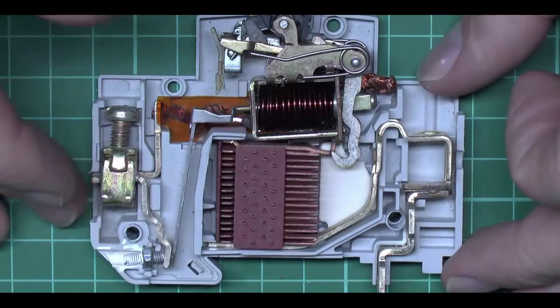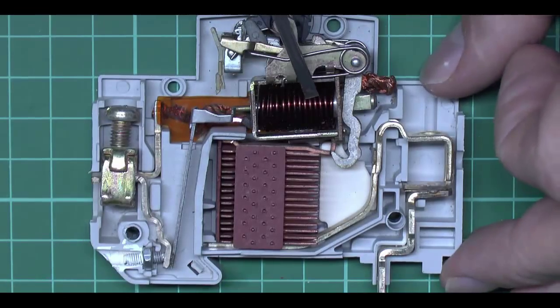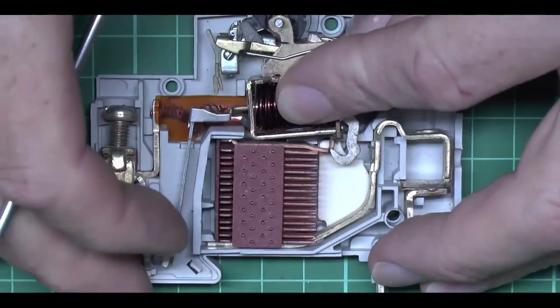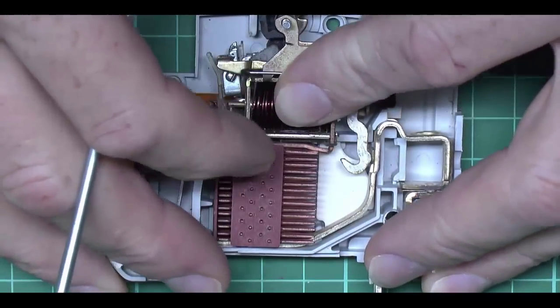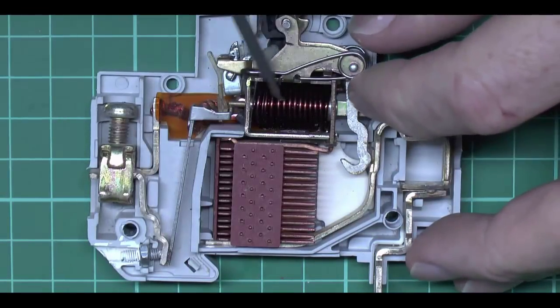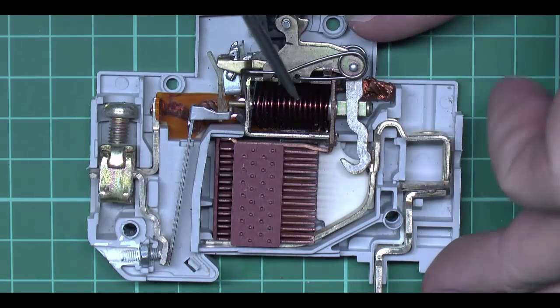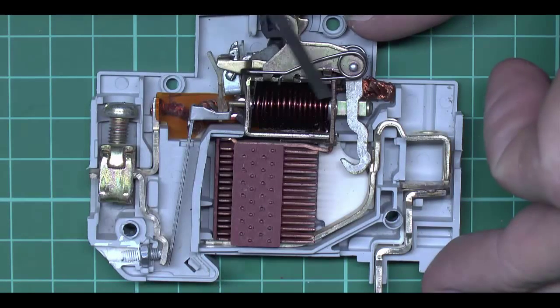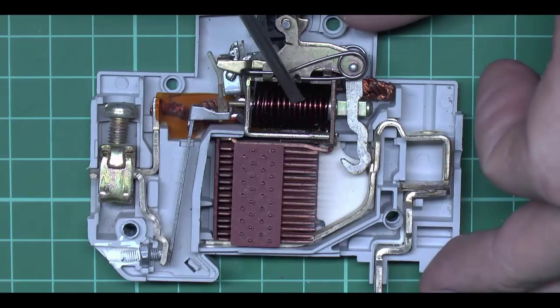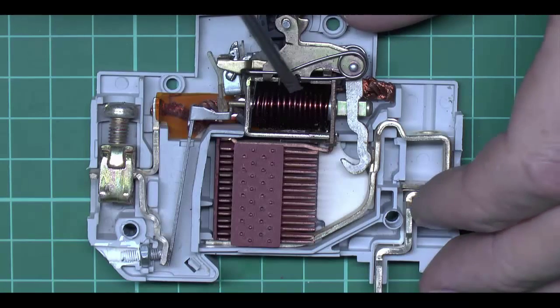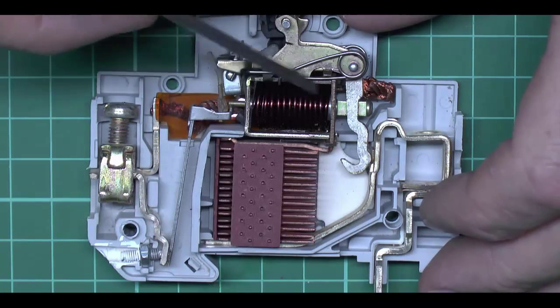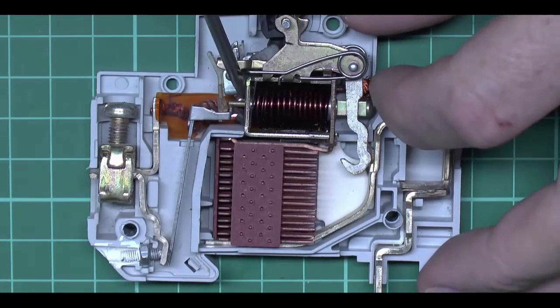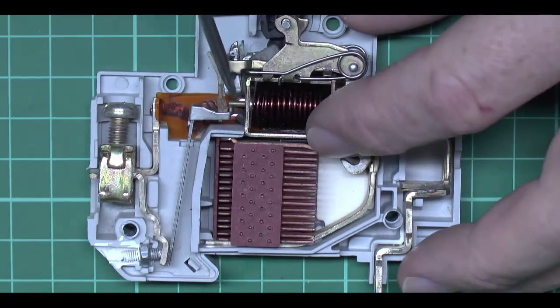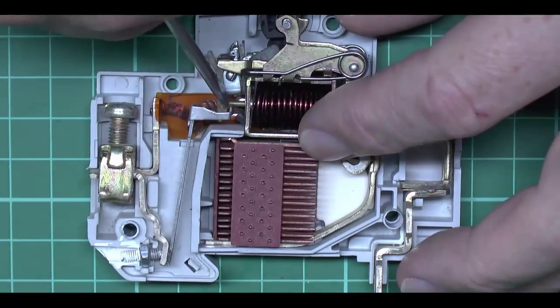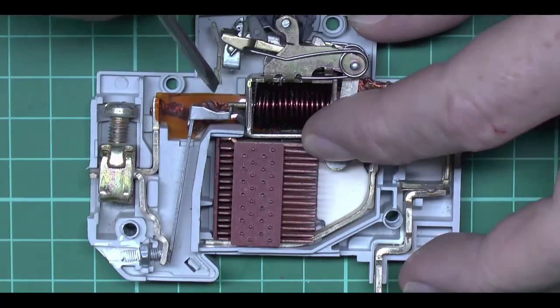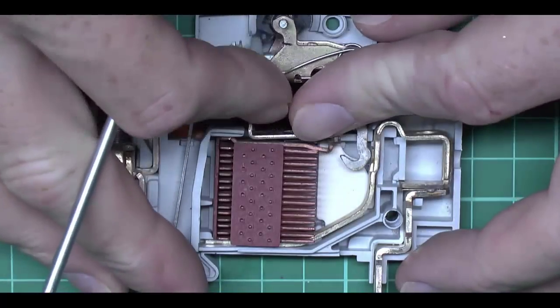Now these things have got two tripping mechanisms, and the first one of which is this coil here. And essentially when the device is in the on position, just place it there, of course current is flowing through this all the time, and in the event of a short circuit, the current that flows here will be extremely large, typically in the order of a few hundred or even several thousand amps, depending on the characteristics of the supply. This will create a magnetic field here, and it will move the pin there, and in this case it will push upwards, and on pushing upwards onto this piece here, it will cause the device to trip, and of course open the contacts at the other side there.